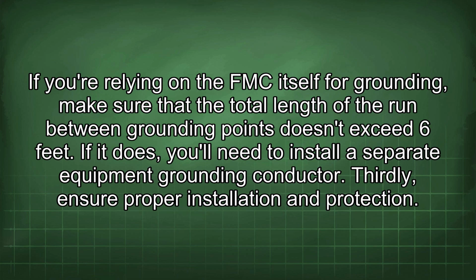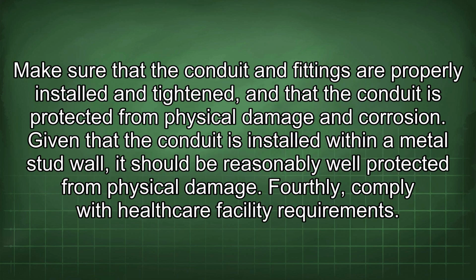If you're relying on the FMC itself for grounding, make sure that the total length of the run between grounding points doesn't exceed 6 feet. If it does, you'll need to install a separate equipment grounding conductor. Thirdly, ensure proper installation and protection. Make sure that the conduit and fittings are properly installed and tightened, and that the conduit is protected from physical damage and corrosion.